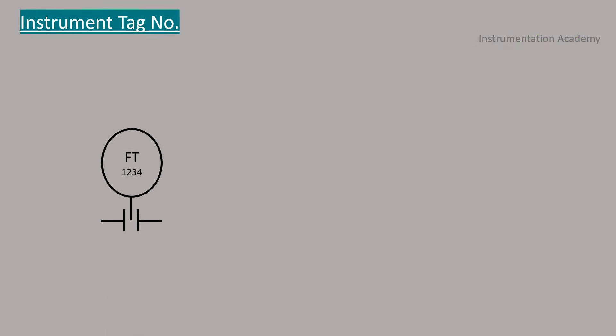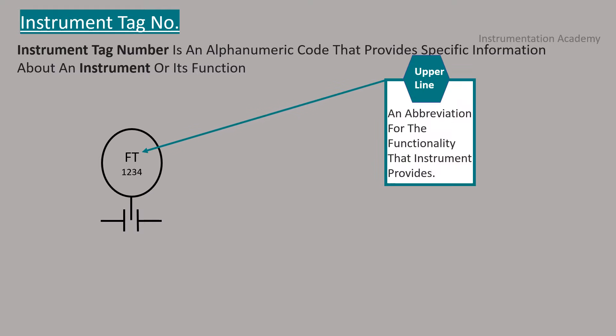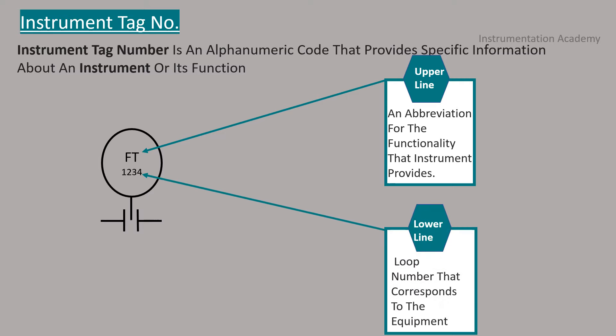Instrument tag number. Instrument tag number is an alpha numeric code that provides specific information about an instrument or its function. Instrument tag number has two lines in it. One is upper line. It is a short form for functionality that instrument provides. The second is lower line. It is a loop number that corresponds to the equipment in the plant. Since most plants have many instruments of same type, the unique number is applied so that each one can be individually identified. This number is known as loop number.